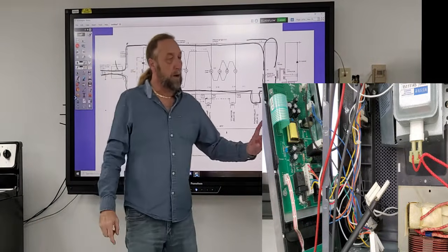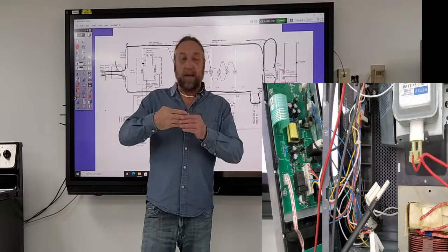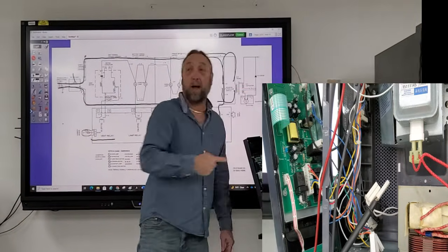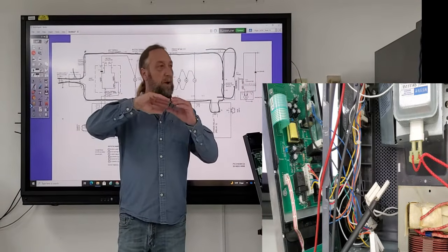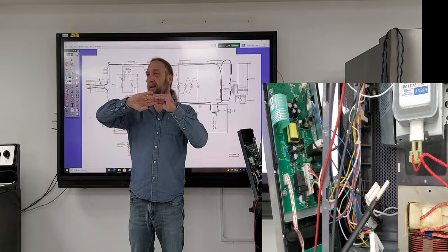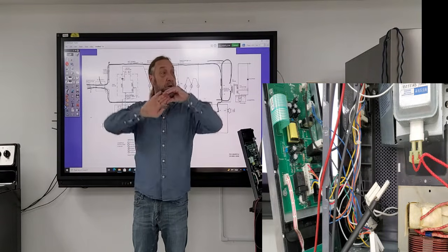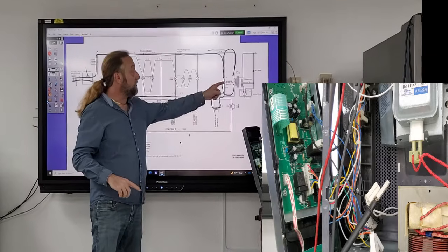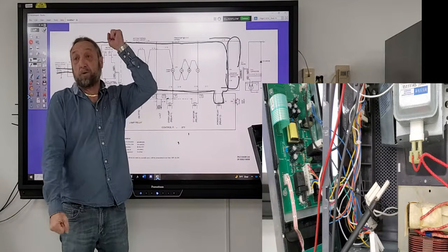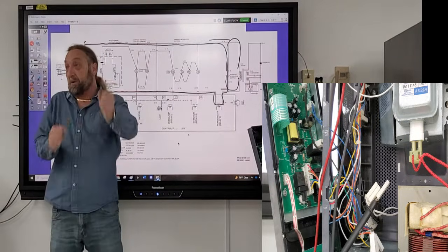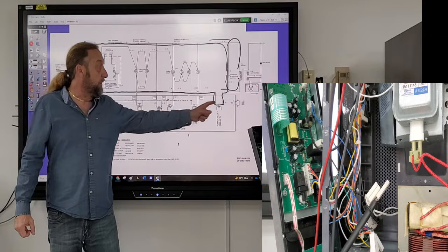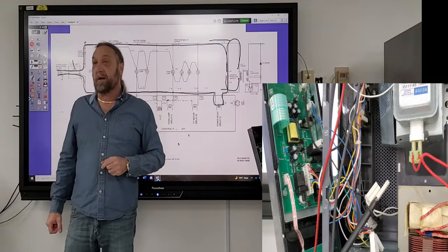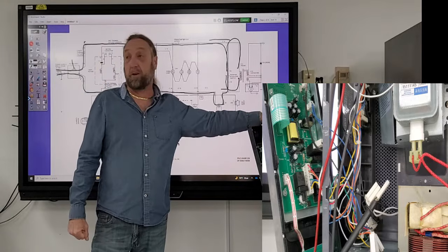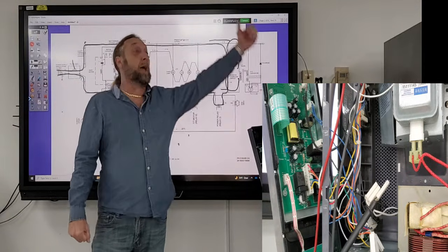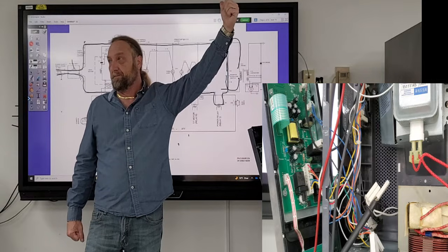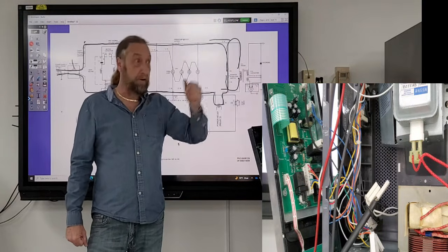But on this design of these switches, if the wire is not plugged firmly onto the switch, the plastic around the wire actually holds the switch steady. If it's not firmly in there, the switch can move, and you can have this switch and this switch close at the same time. It's not supposed to. One's supposed to open and the other one closes before they both do it. So if it opened and this relay here and those two are closed at the same time, it's gone to the point now that it not only blows the fuse here, sometimes it avoids the fuse and cuts the circuit breaker in the customer's home. Like that fuse doesn't even trip, the voltage short is so high.